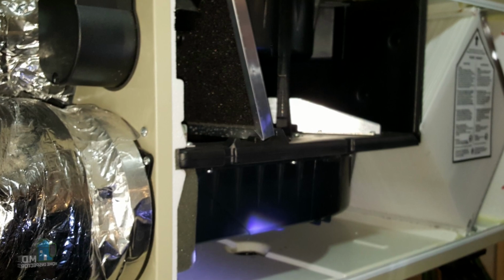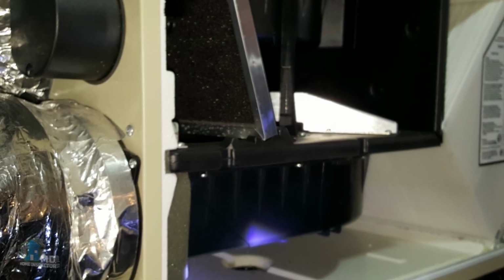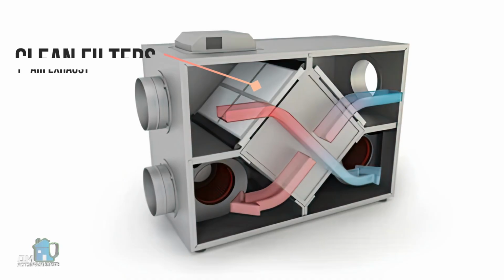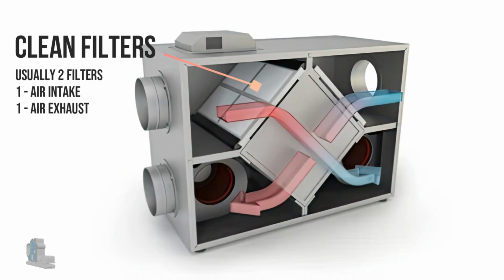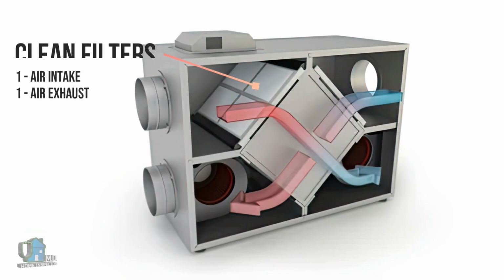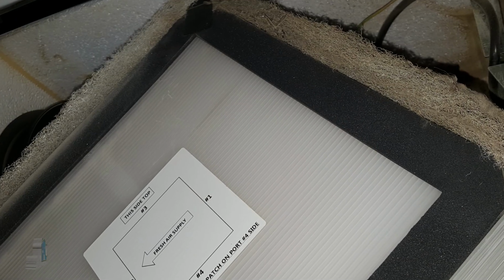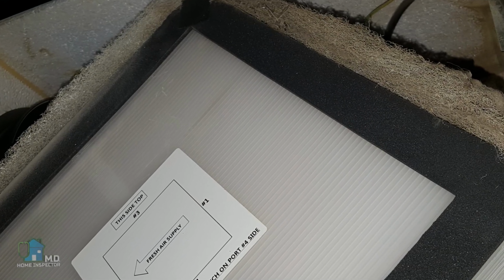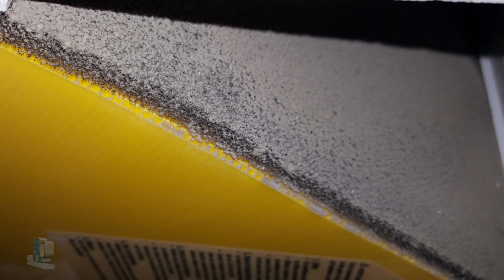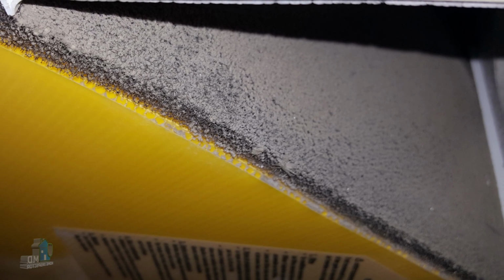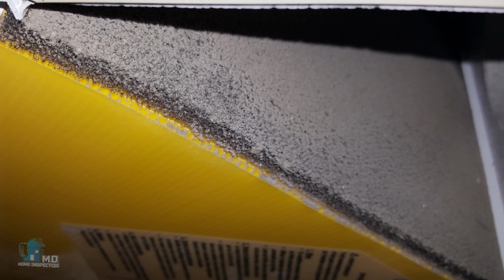And what about the maintenance of an HRV? Well, maintenance is fairly easy. Much like the furnace, for the most part, all you have to do is replace the filters in the HRV. And there should be only 2 filters, one for the fresh air intake and the other for the exhaust air. Depending on the type, most will allow you to just clean the filters every 3 months or so. Or you can replace the filters every 6 months depending on whether you have more people or pets in the house. And just like the furnace filters, it's very important that you clean or replace these filters.